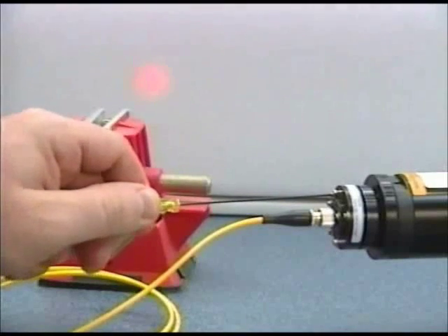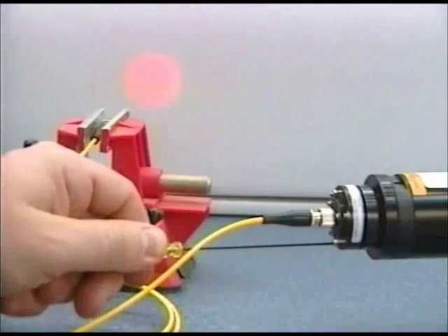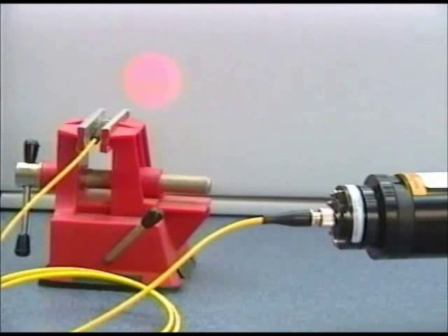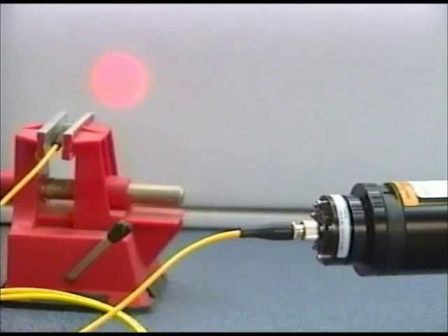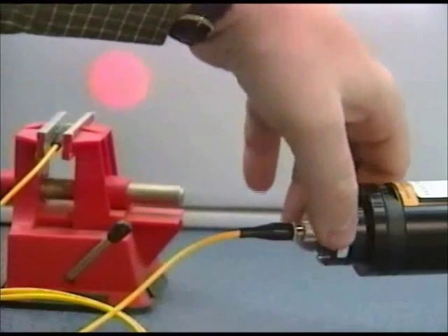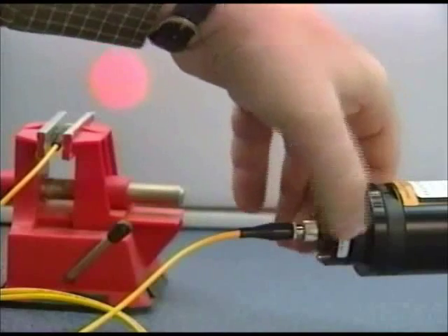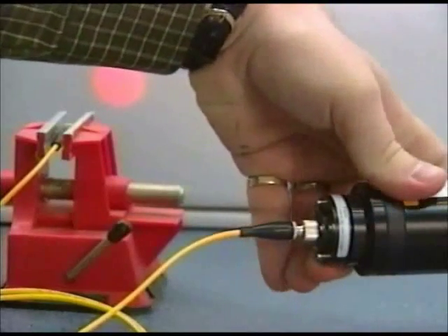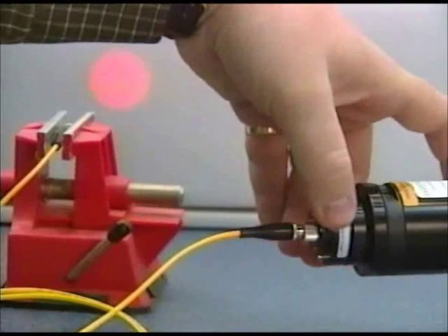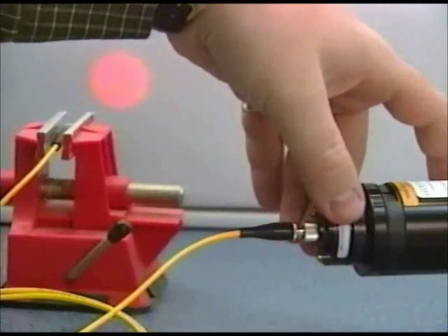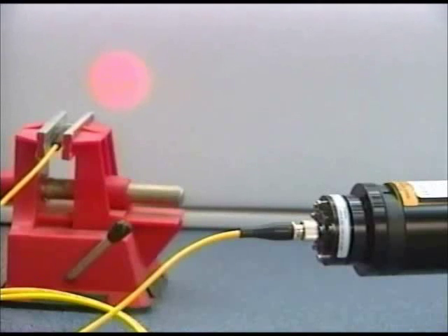For the purpose of the presentation here, I'm demonstrating it strictly on a screen. If you really wanted to measure things properly, you would hook the output from this fiber to an optical power meter and measure directly how much light is coming through. You may find it necessary to do a little bit of tweaking to the centering. So what you would do is you would look at the power from the fiber while doing that lateral adjustment. It's going to be a lot harder to do than before. And you may have to readjust the tilt afterwards. But if you've done it right, you should get quite a bit of power.